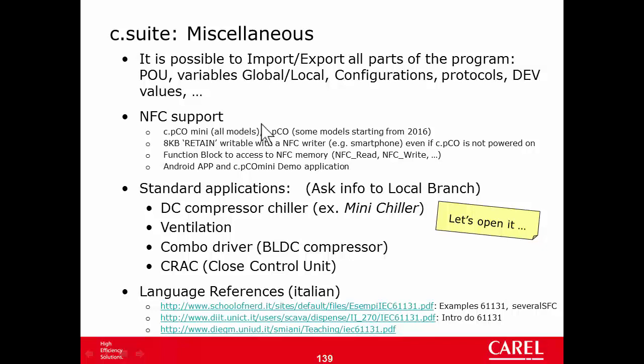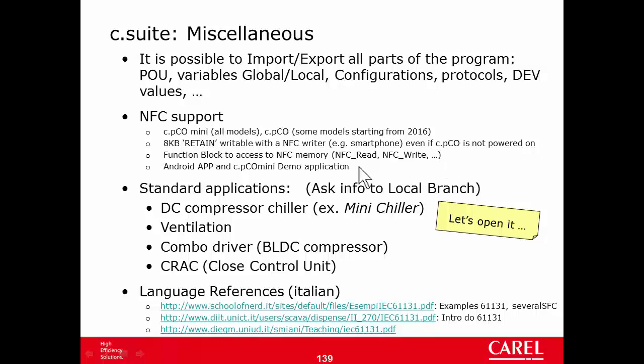NFC support: all models of c.pCO mini and some models of the newer hardware version of c.pCO have an NFC tag. It is 8KB, which is basically a retained memory that can be read or written using a compatible NFC writer like the ones on most popular smartphones. It is possible to read and write it even when the c.pCO is not powered on. From the application point of view, you can read or write that memory using specific function blocks — NFC Read and NFC Write. A demo application for c.pCO mini and an Android app are available to test this feature.